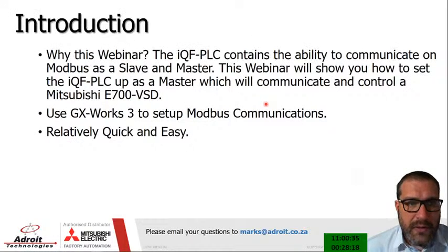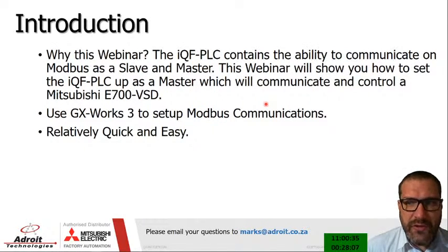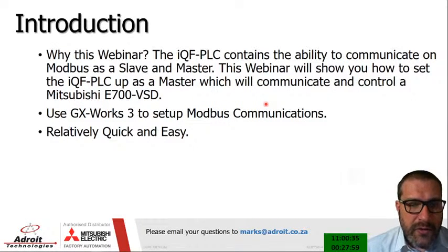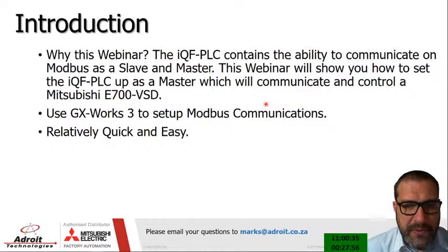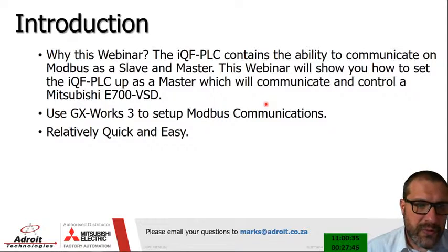Okay, so let's talk about this webinar. Why are we doing this webinar? The PLC contains the ability to communicate on Modbus as a slave and a master. In this webinar, I will show you how to set up the iQF-PLC as a master, which will communicate with and control the Mitsubishi E700 VSD. As always, we're going to use GXWorks 3 to set up the Modbus communication, so in other words, no third-party application at all. This is all done through GXWorks 3, and it is relatively quick and easy. For me, of course; for you it might not be that easy the first time, but when you do it the second, third time, it's a lot easier.